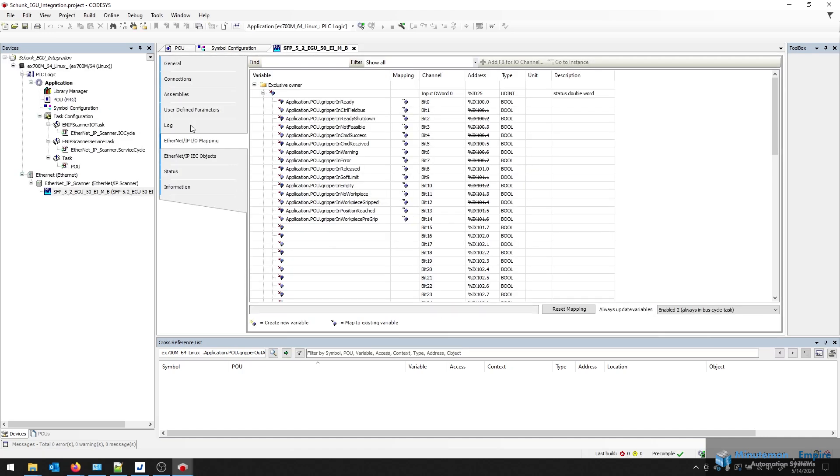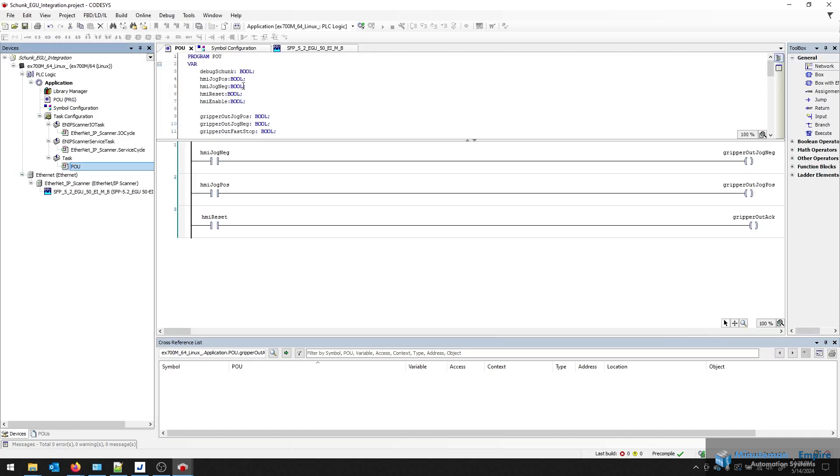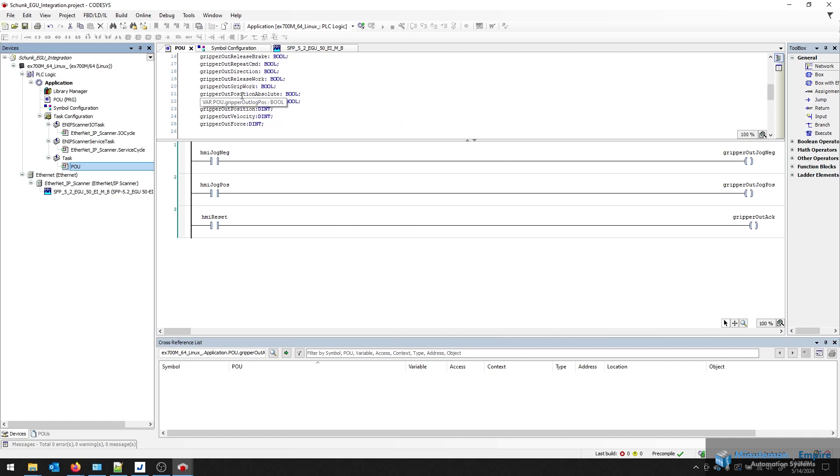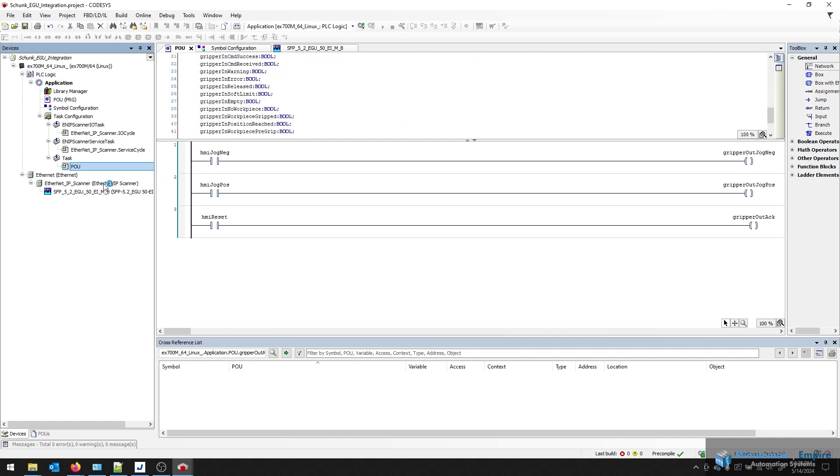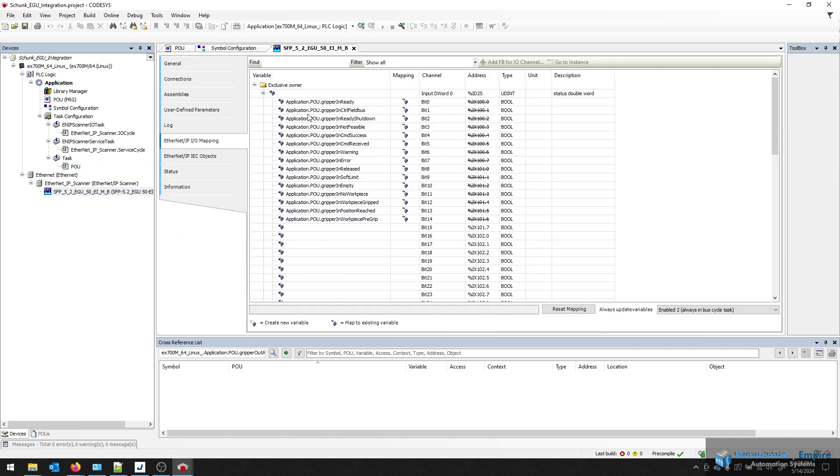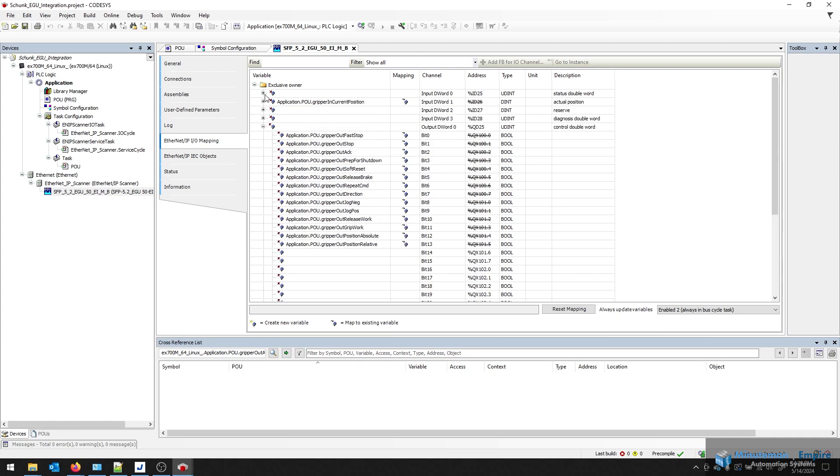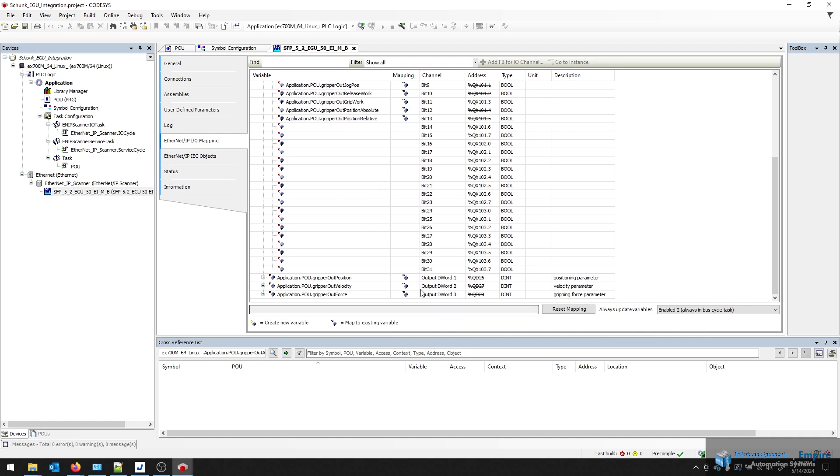Here, you'll see I've had my project with my tags. So I've created a list of variables that are the various inputs and outputs. I've even created some HMI IO so I can control this from the screen and tied them to the jog negative, positive, acknowledge for resetting errors. In my Schunk IO map here, you'll see the various mappings for the various status and control words. At the bottom, you'll also see the gripper output position, velocity, and force.